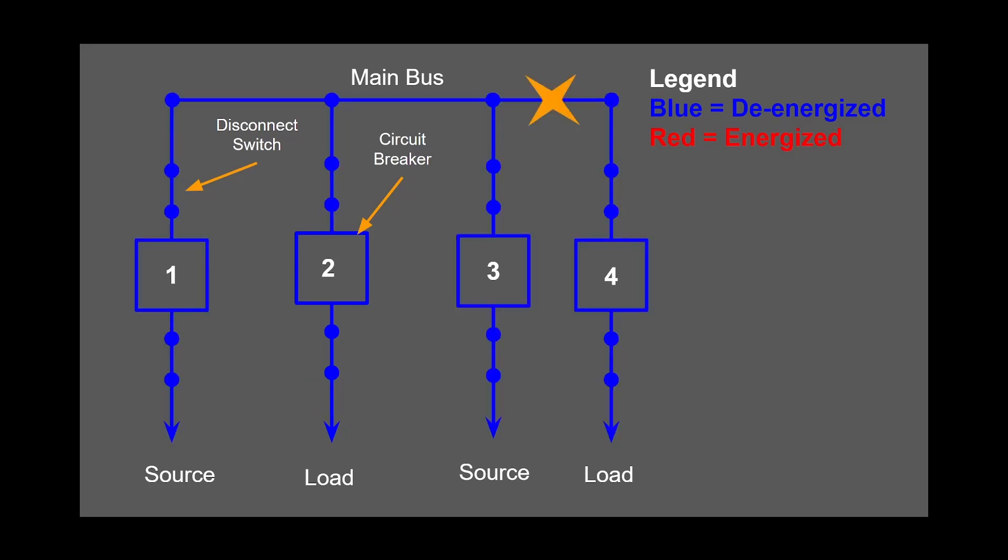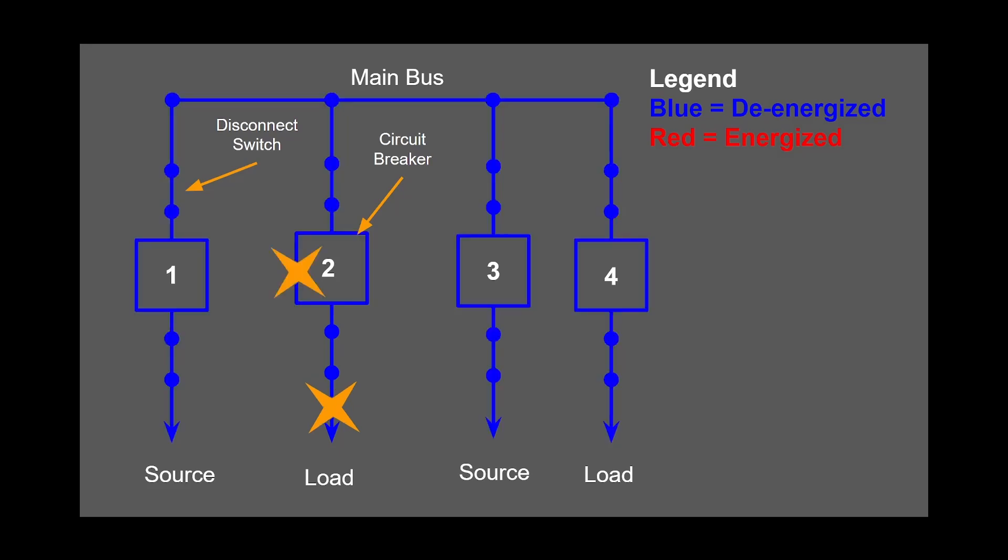If we get a fault on the bus side of the breaker, then the whole system will have to go down to prevent this fault from going to the other lines. You would have to trip all breakers in this case. Additionally, if a fault happens on the line side of the breaker and the breaker happens to fail, meaning the breaker didn't trip, then the entire substation would experience an outage. Ultimately, making this system low on the reliability scale.